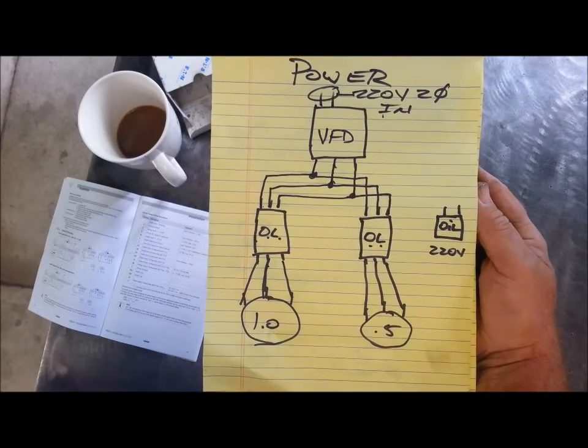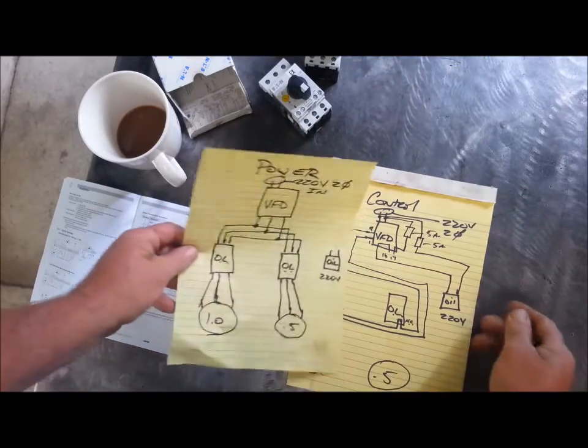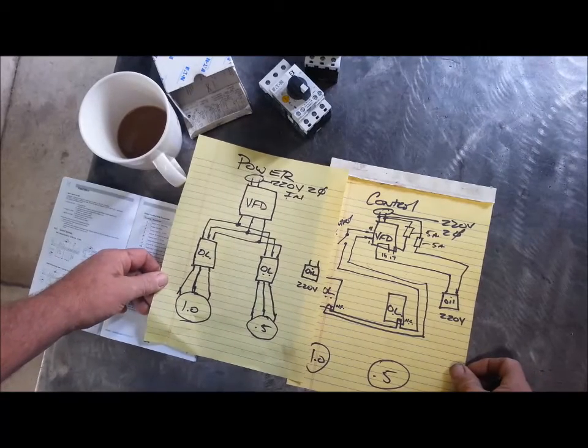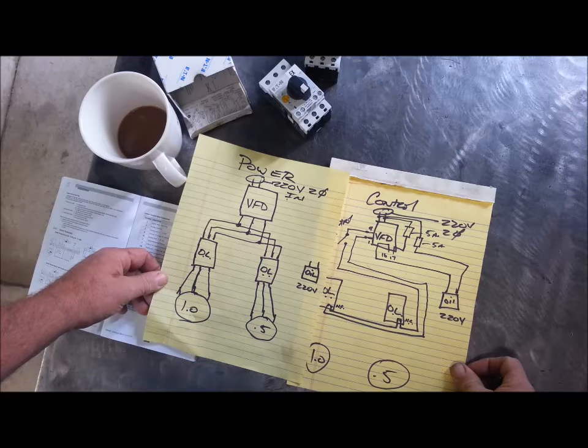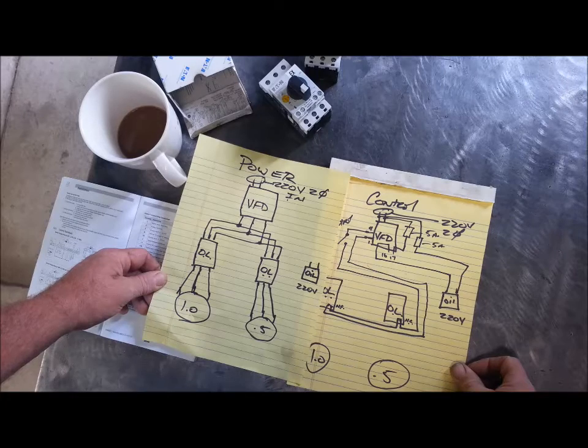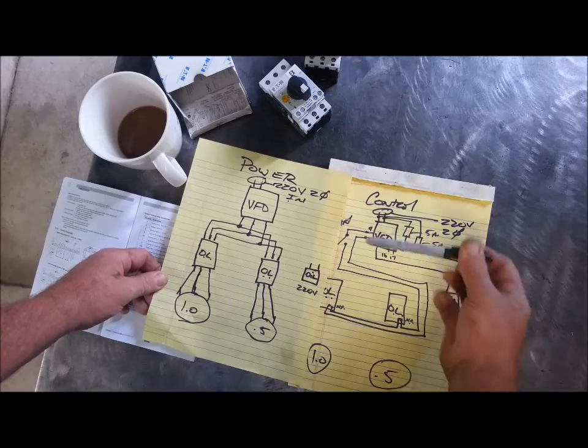But that's how I intend to run dissimilar motors off of a VFD. I'm not using any speed control, no speed reference. The only thing I'm using the VFD to do is generate the third phase. And this may look overcomplicated to you, but changing out the motors isn't really an option. On the Boyer-Schultz, the spindle motor is an odd duck, and it would be very difficult to get it in single phase. And for $300, I can get a VFD.